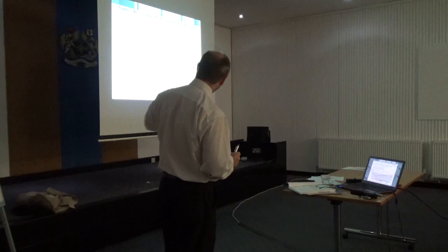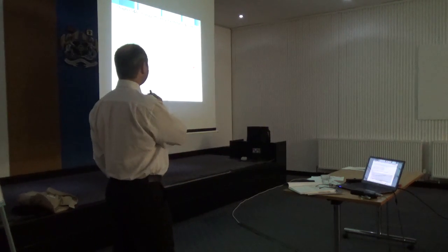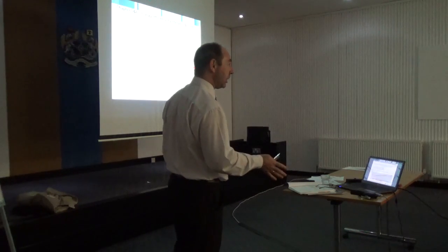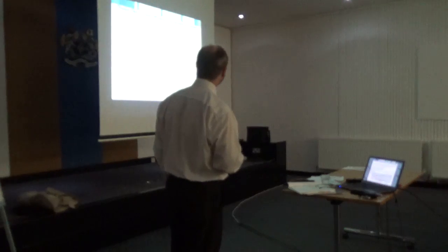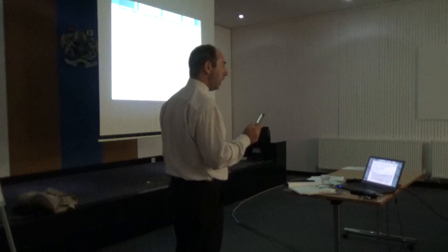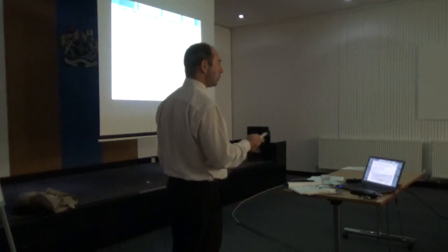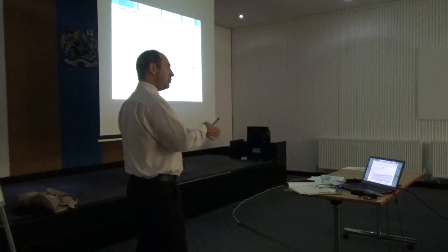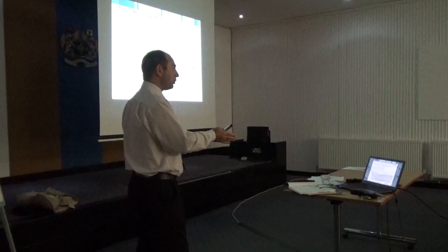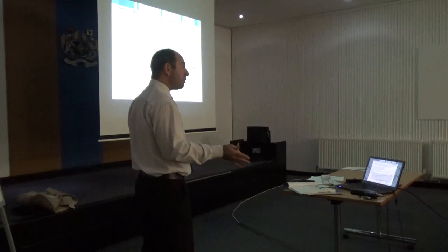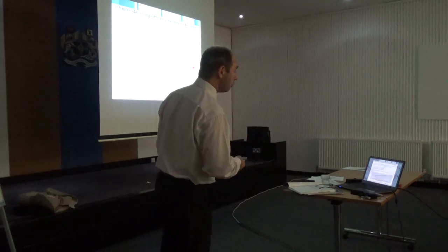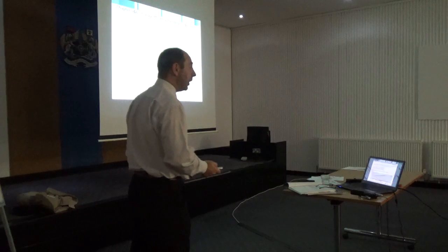And what I've shown at the bottom there, again, you may have seen it before, is an indication of the range from manual control, which to be fair has a place, let's not discount it, manual controls do work, right through to integrated controls. The more you move to the right, the higher the cost. And that's not only capital cost, that's ongoing maintenance cost, ongoing cost of change, increasing rate of obsolescence, the list goes on. So again, my message here is, if you don't need it to be integrated, then don't. A bulk standard, low-end building management system might be okay. Proportionate, appropriate to the task. And if you're further interested, Knowledge Series 04 is quite old now, but again, still some very good stuff in there.